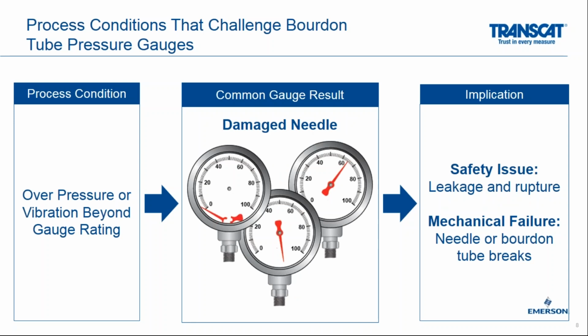The next one is overpressure or vibration just beyond the gauge rating. And I talked about this before when it comes to overpressure, but there's another thing that can happen, and that's the actual needle can be damaged. You know, not only can there be a rupture of a Bourdon tube, but with all of those different linkages, if anywhere in that process something gets damaged, including the needle, whether the needle itself is broken, in which case you don't know what's going on in your process, or the needle is simply showing something that's inaccurate because it's broken. This can be a safety issue, certainly, if there is a leakage or rupture, but the mechanical failure also means that you're going to need a new gauge. And it's possible you may not even know that you need a new gauge because the needle might point somewhere. It's just not pointing in the place it needs to.